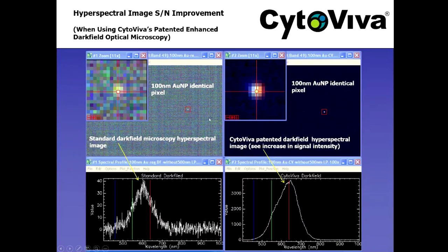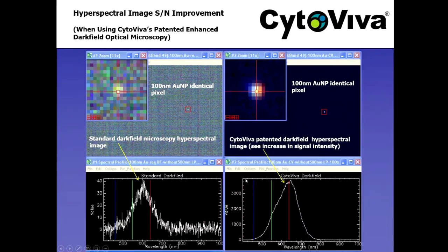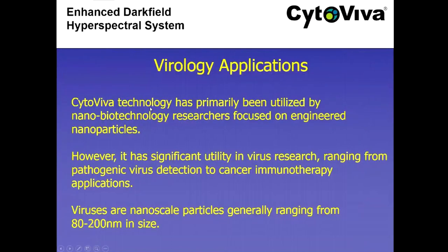This image of a 100 nanometer gold particle demonstrates how hyperspectral imaging benefits from the enhanced dark field optics. Using the exact same particle and settings — standard dark field on the left versus CytoViva enhanced dark field on the right — you can see lots of noise and not much amplitude on the left versus hardly any noise and plenty of amplitude on the right. All spectroscopy is dependent on good signal-to-noise to produce quality data.